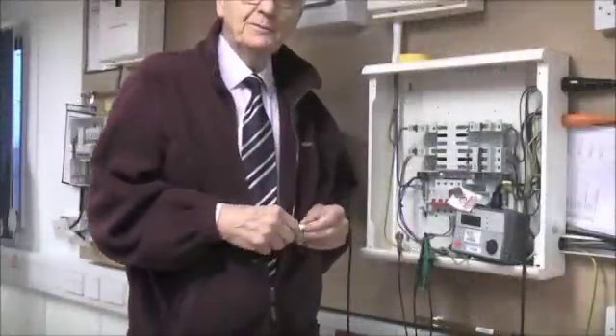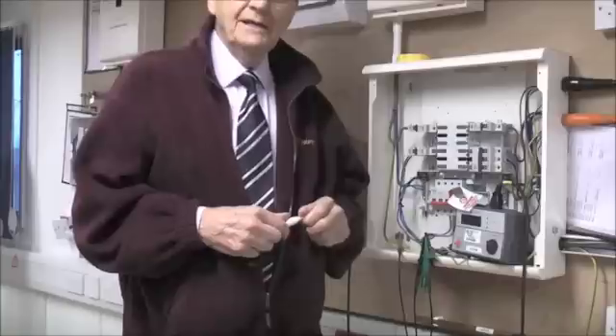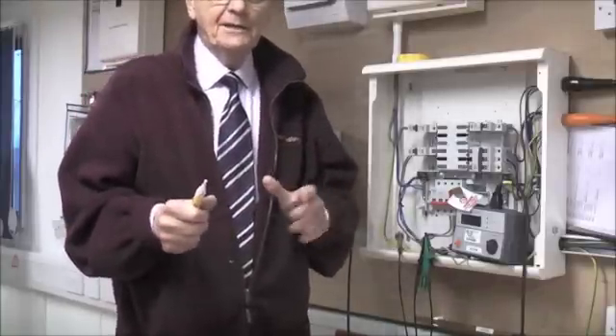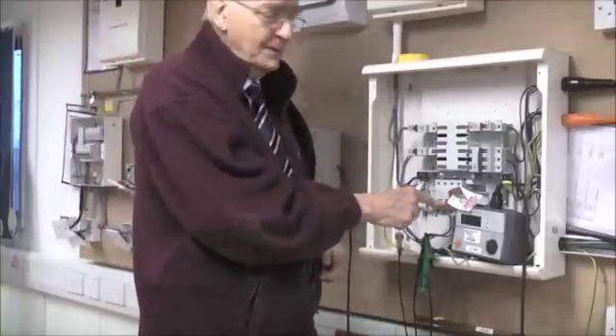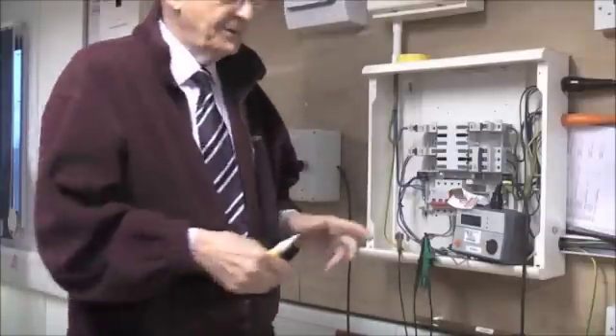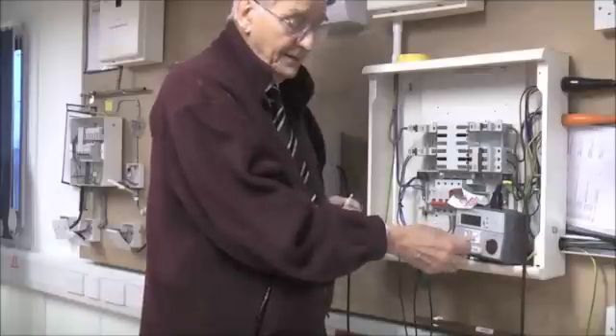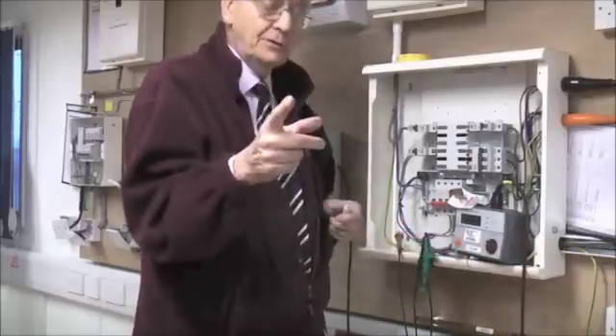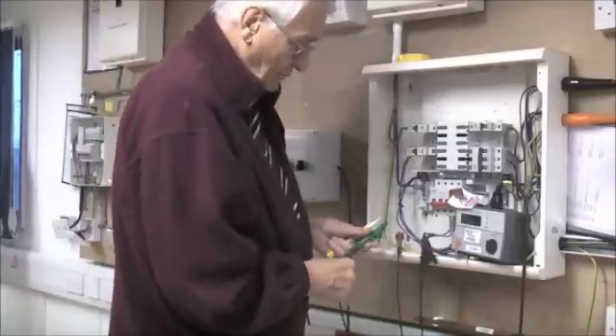Ready to start the loop impedance testing, but before we do I want to remind you that this video is only a demonstration and it's no way to give you competence or authorization. You have to get that elsewhere. So with the supply switched off and the warning label in place and the switch locked off, I'm satisfied that this board is safely isolated. This will permit me to remove the earth connection which I've already done, meaning that I've only got this single earth connection back to the star point of the transformer and back down to the earth connection which is here.